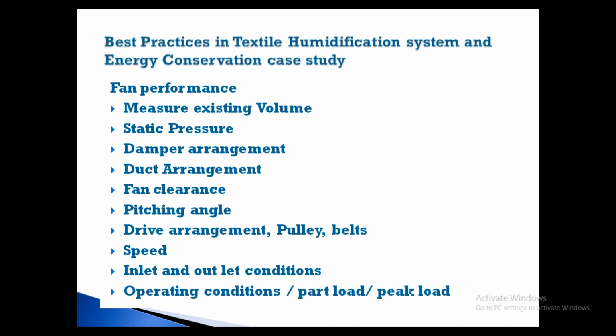So when you go for belt drive for axial flow fans, there will be a shaft, two pulley systems, and a belt drive, and there will be slippage loss. So mostly in supply air and the humidification system, direct driven fans are used. Earlier days it was belt driven. So you have the only option of either changing the fan speed by frequency drive or pulley, or by blade angle. You are reducing the power. This is the only option available for direct driven fans.